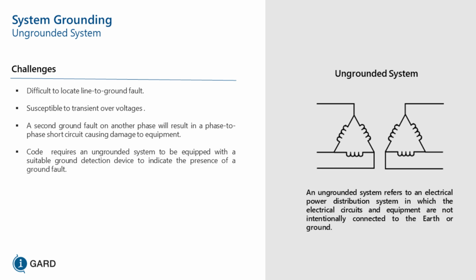When it contacts ground, it needs to go somewhere. So ground fault current always has to return back to its source. Because the system is ungrounded, there is no return path. The only path you have for the current to go in an ungrounded system is to the other phases through the capacitive coupling, and we'll discuss that a little bit. It's very difficult to locate a ground fault in an ungrounded system because there's nothing to detect.